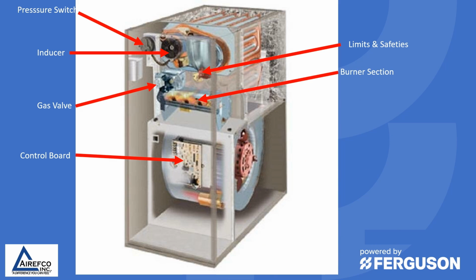The burner section needs to be observed when the furnace is operating to make sure that you have a clean blue flame and that the flames are going down the tubes of the heat exchanger properly. Any kind of rollback or feathering flames could indicate a problem either with the induced draft motor or with the heat exchanger itself.